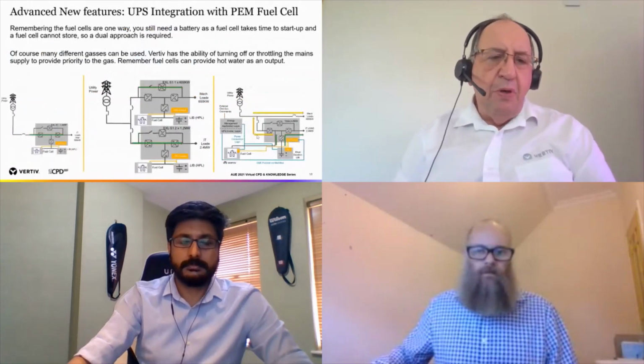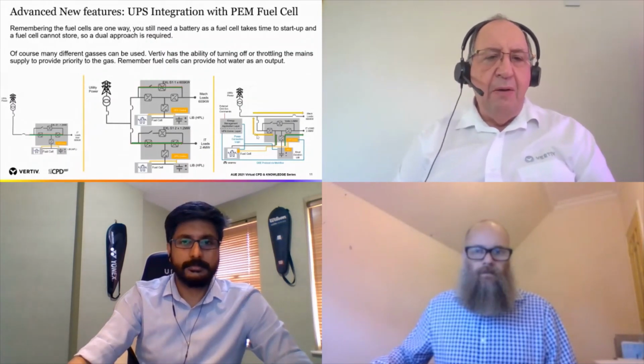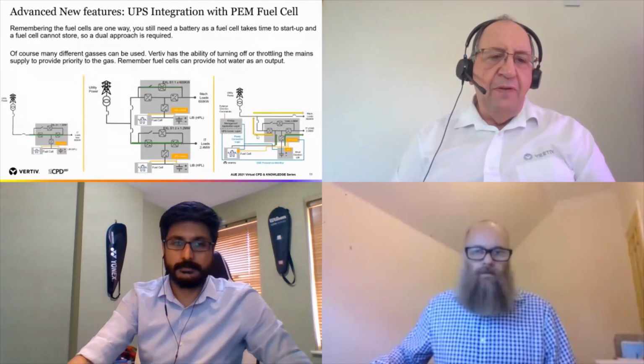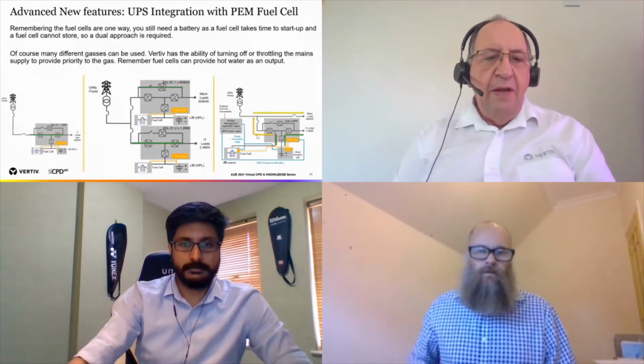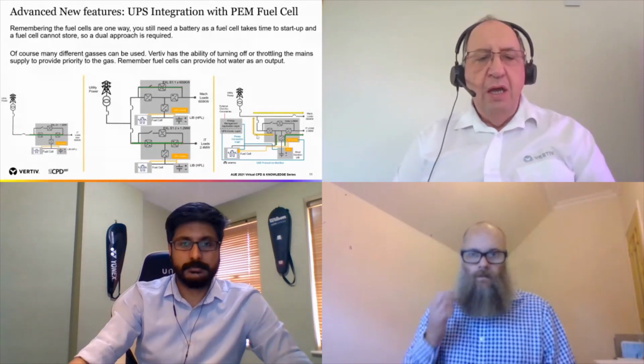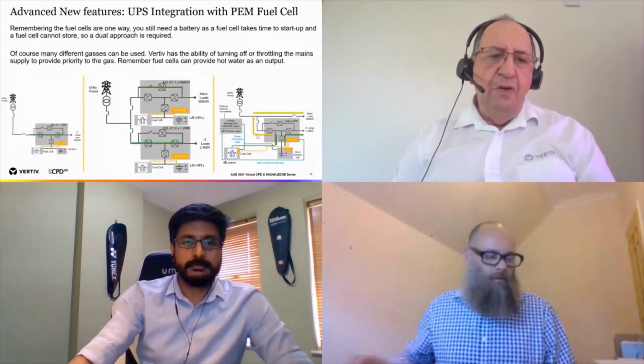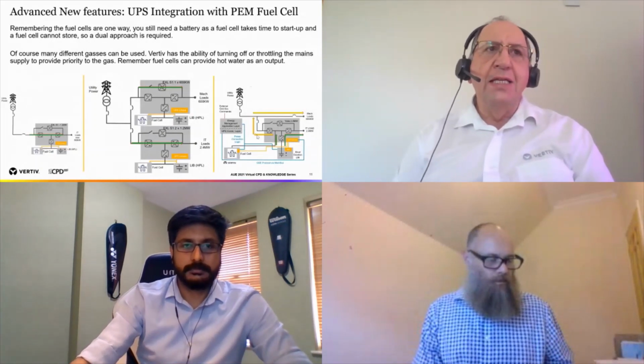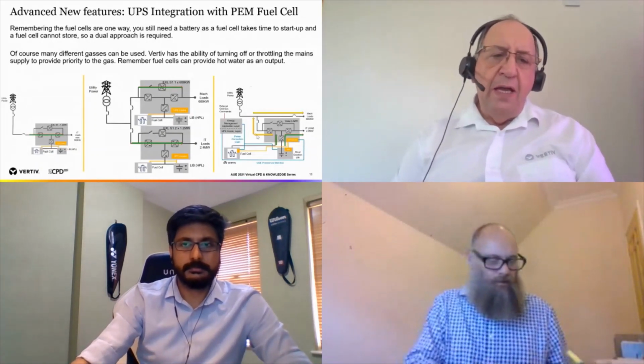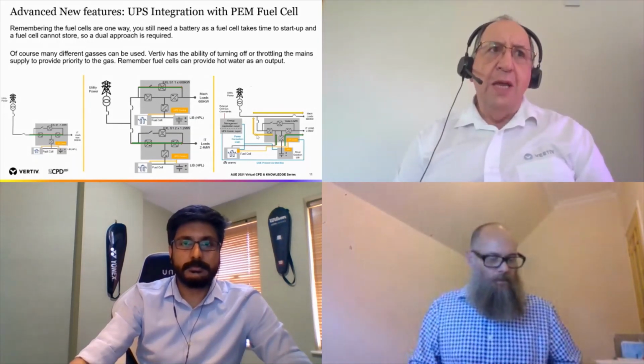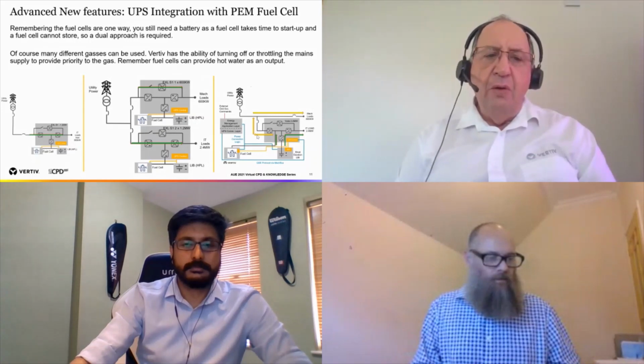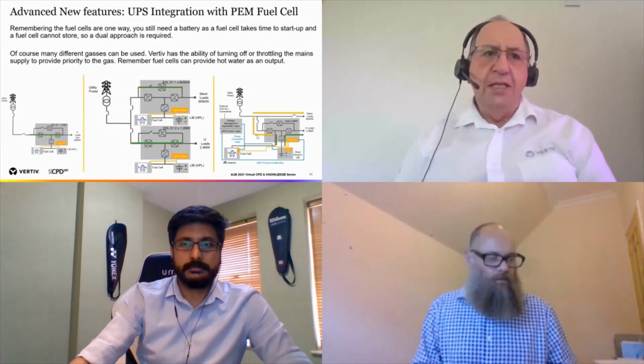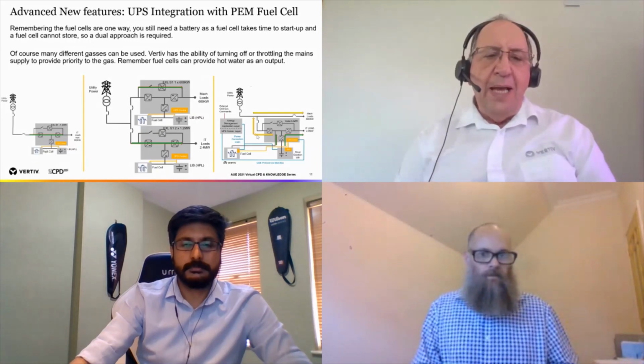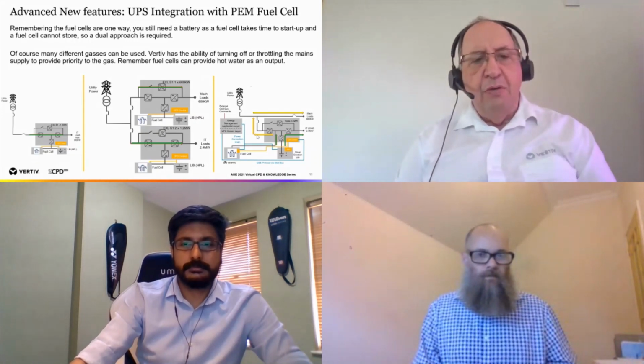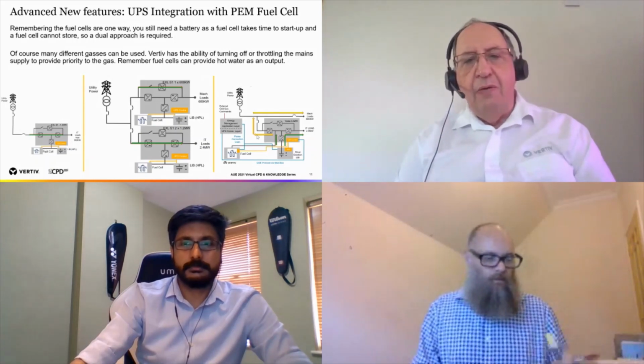So if we look at this bottom left hand diagram, there's our UPS with the utility power coming in, and on the bottom left hand side you can see there's a fuel cell, and then on the right hand side there's a lithium ion battery. The idea is that the fuel cell takes a few seconds to get going. So if there's a power failure, then the lithium ion battery will step in to provide the current for the load. Once the fuel cell gets up to full power, then we back off the lithium ion battery and the fuel cell carries on providing the power out.